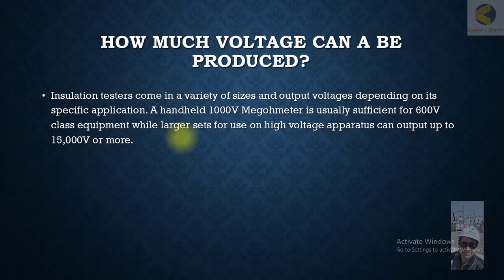Now IEEE has defined new requirements: if the insulation size is more than 12kV, the insulation should be tested with a 10kV IR tester. So if you want to test MV cables rated more than 12kV, the trend now is to test them with a 10kV insulation tester. This is a basic introduction about megger selection.